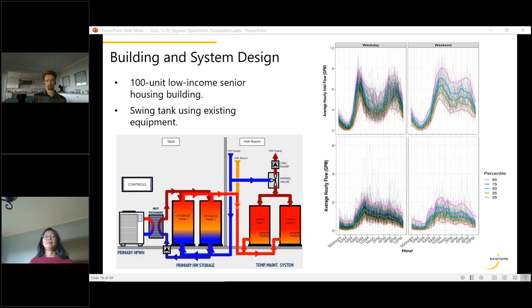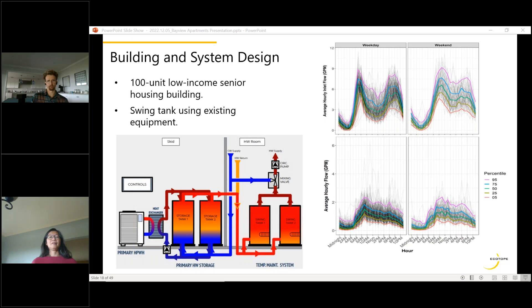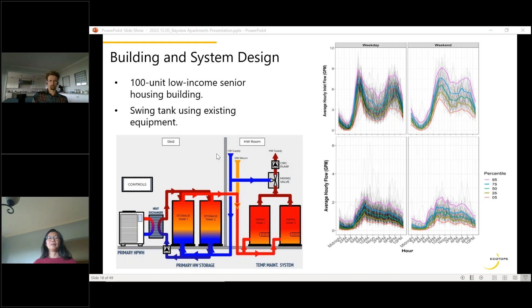Tony highlights key learnings: the heat exchanger in the system is a new piece of equipment added as a US code requirement — a double barrier that isn't a Mitsubishi requirement in Japan — illustrating the kinds of US-specific code challenges encountered. The existing resistance tanks were kept for the swing tank, but a potential future improvement would be to make the swing tank makeup heat also heat-pump-driven. The overarching lesson: instrument thoroughly, learn from it, document it, and share it so future installations become better and more refined.